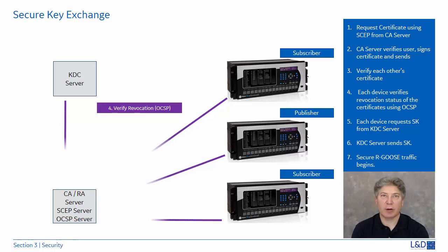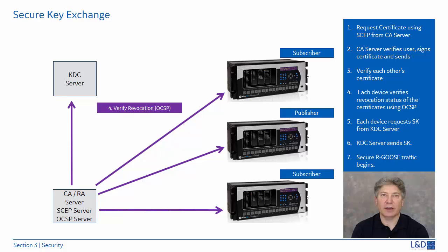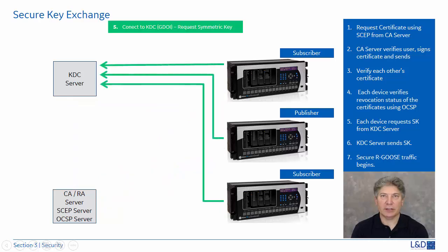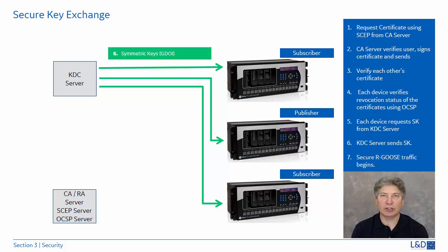Next, each party — the KDC, publisher, and subscribers — contacts the registration authority using the Online Certificate Status Protocol. They send their own certificate and the other device's certificate for validity and revocation status. Each device, whether subscriber or publisher, also holds a copy of the KDC certificate and sends both copies for verification to the registration authority. If verification succeeds, the devices contact the KDC for a symmetric key. The KDC sends a symmetric key to the devices, which is used for signing and encrypting the routable GOOSE message. As per the standard, these keys must be updated at least once every two days through re-keying — either via a pull mechanism where each device repeats the exchange steps, or a push mechanism where the KDC server sends new keys to all group members in one multicast message.